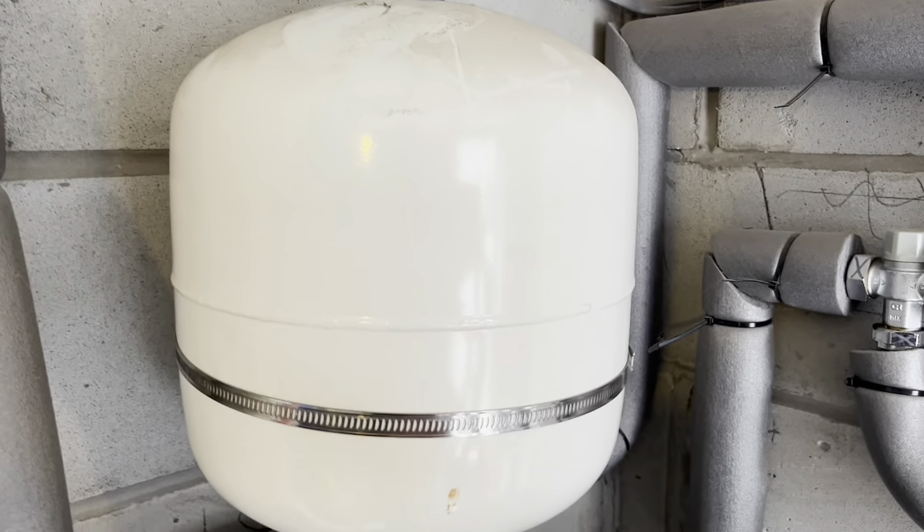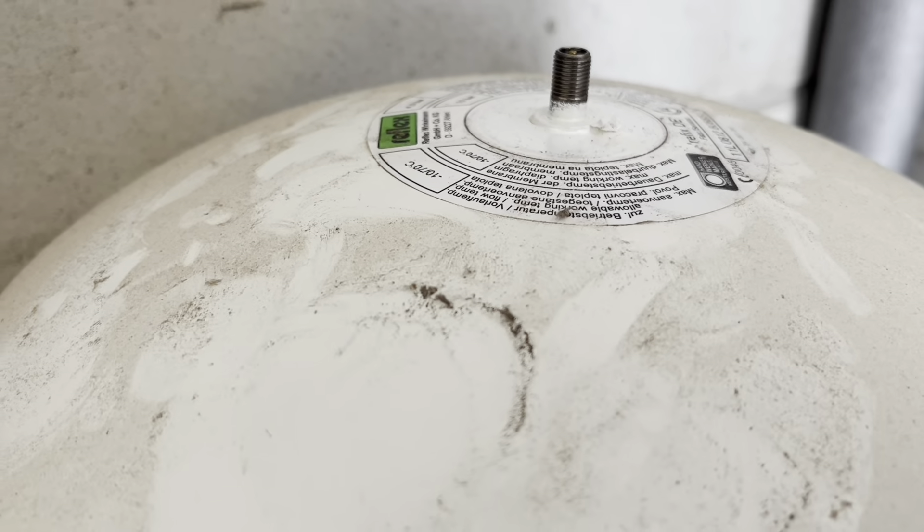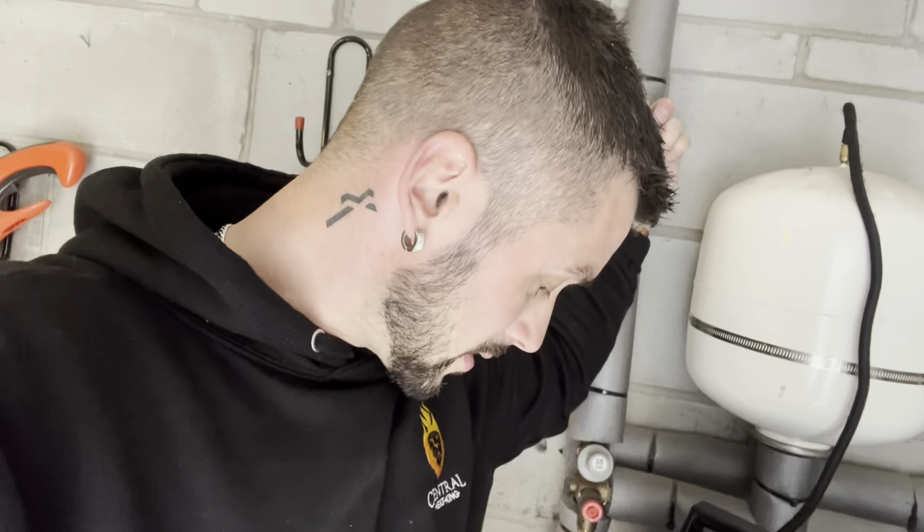Before I turn the water on, might as well recharge this - you'd only have to turn it back off again to do it. We're recharging an expansion vessel on an unvented cylinder. Water off - either the stop tap to the whole house or the stop tap to the unvented cylinder itself. Open a hot tap or outlet, then recharge it. It's showing 3.15 bar. The data sticker says four bar recommended on this Vaillant product, so I'm going to recharge it to four. Check your Schrader valve after for leaks. That's that bit done.